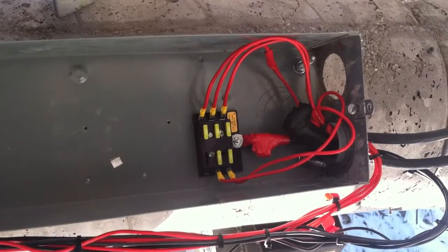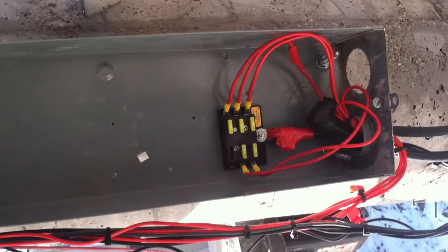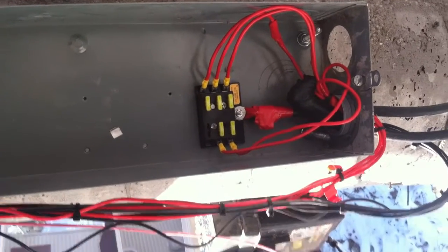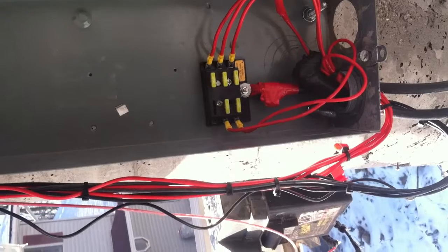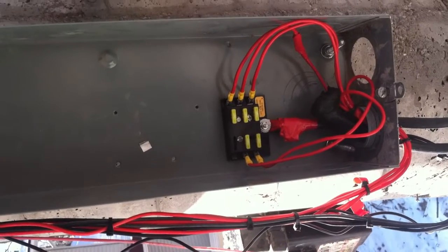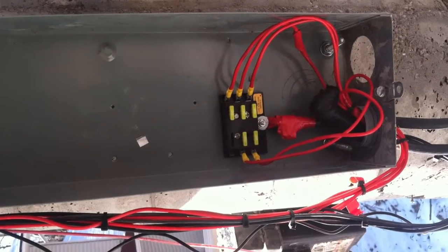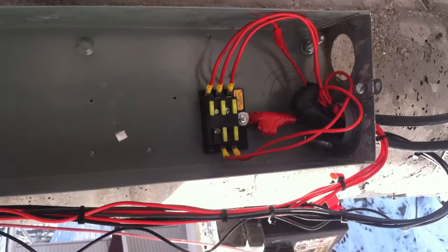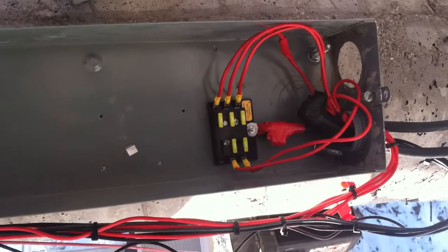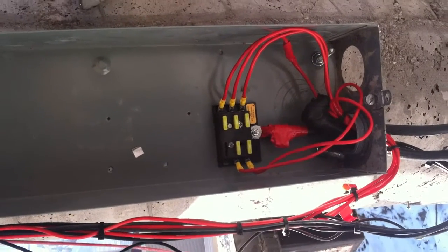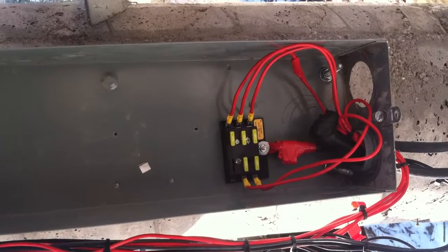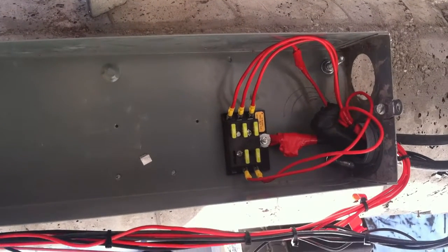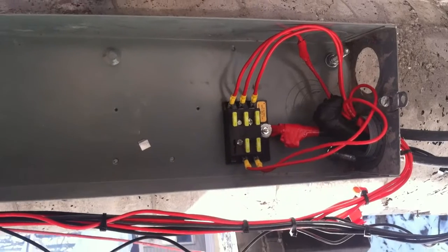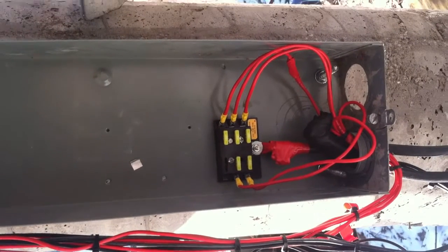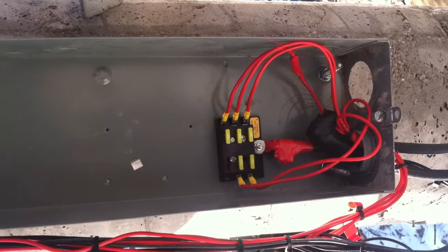So we have 20 panels in a 24 volt configuration. So two panels together is a series, and two of those series connect into a parallel and come down into one wire. So there's five wires for 20 panels. You want to put a fuse in between the parallels, so if there's a short on one of the panels, it doesn't backfeed through a wire and fry a wire and cause a fire.